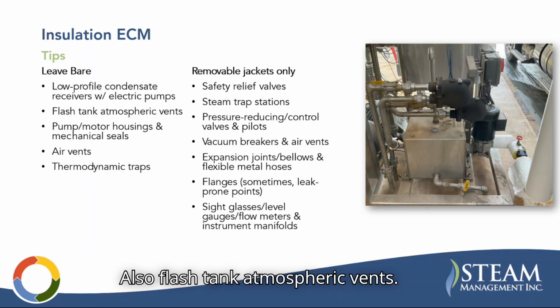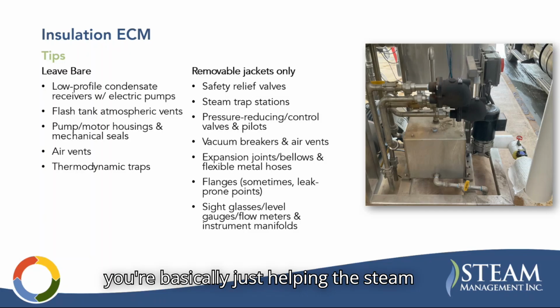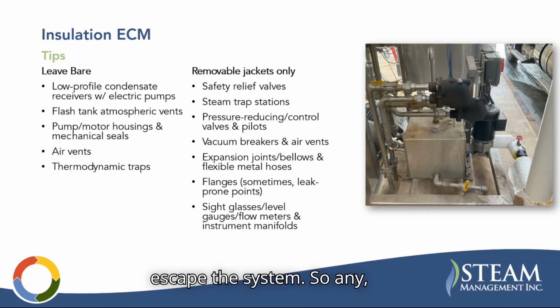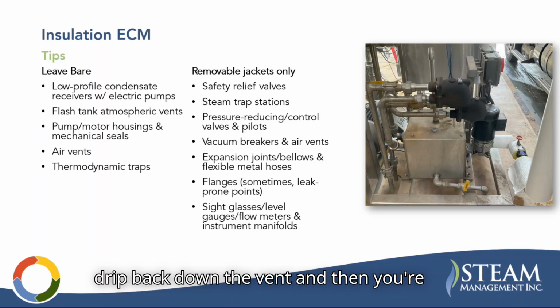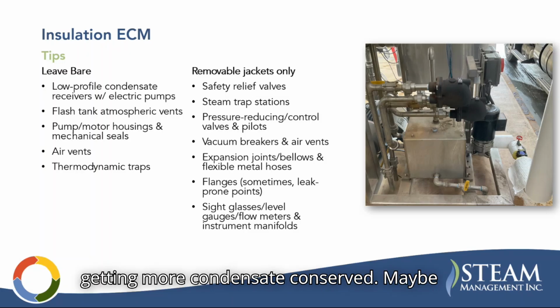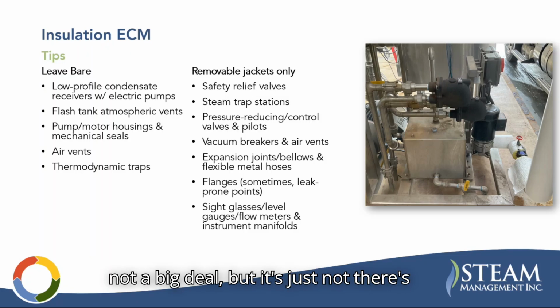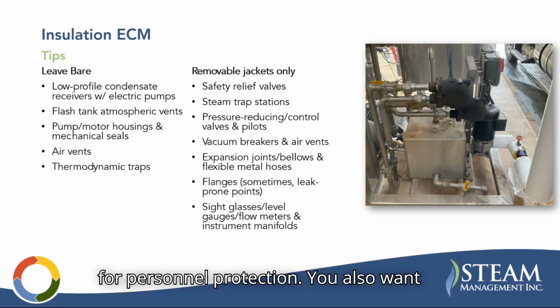Also, flash tank atmospheric vents. So if you think about a vent coming from, say, a tank like this, if you insulate the vent, then you're basically just helping the steam escape the system. If it was to lose energy, it will turn back into condensate and possibly drip back down the vent, and then you're getting more condensate conserved. Maybe not a big deal, but there's no benefit of insulating it unless it's for personnel protection.